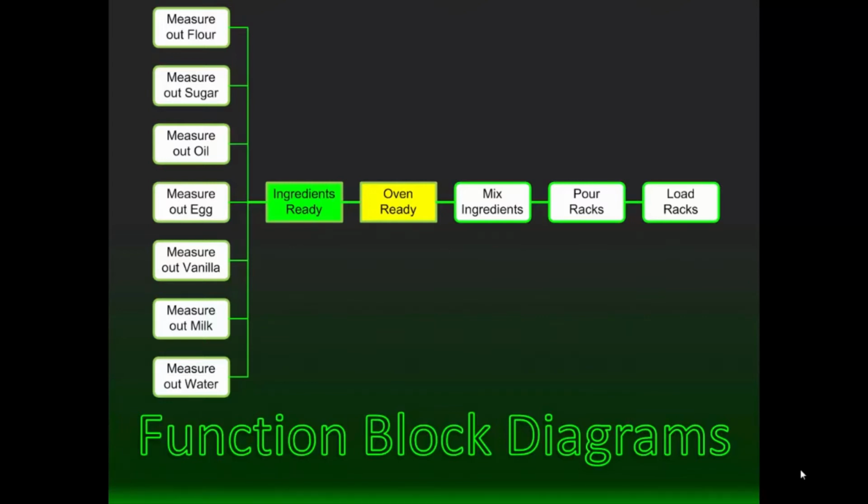But if you were actually considering this process for manufacturing, the powders would probably be loss-in-weight feeders, and the liquids would come from tanks through valving, and you would even have to consider things like dribble from the valve, because when you shut the valve off, the liquid keeps flowing into wherever you're mixing the ingredients. However, you wouldn't really start anything until all the ingredients were ready.